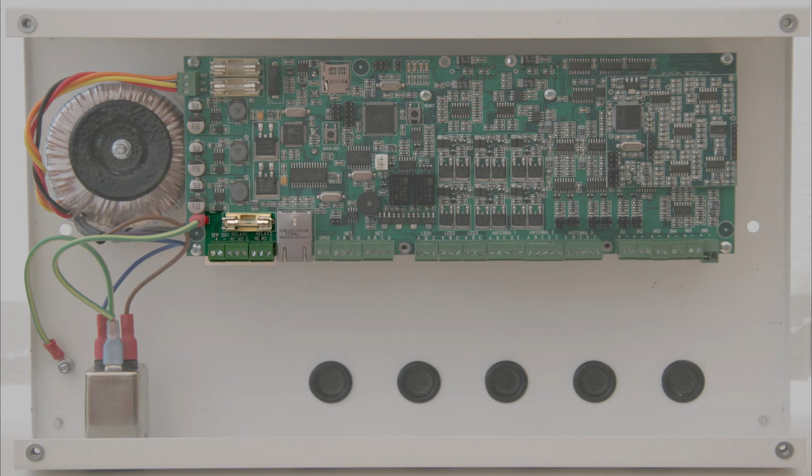At the very bottom left of the board are the two relay outputs, which are voltage free, normally open, normally closed, changeover relays, and a fused 12 volt output. The fused 12 volt output is useful for driving sounders and buzzers. This is fused with the fuse you can see in the picture.